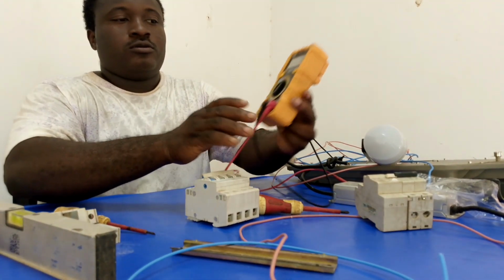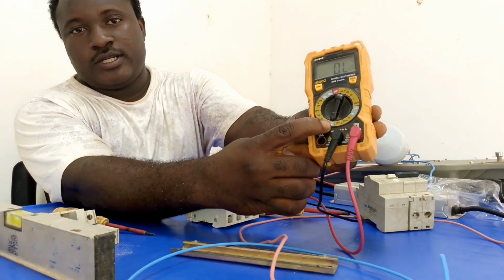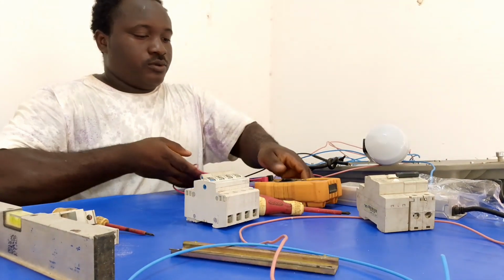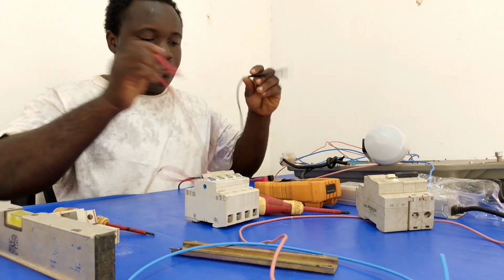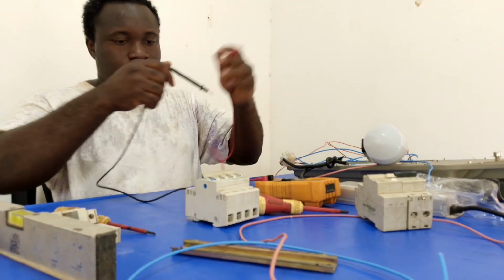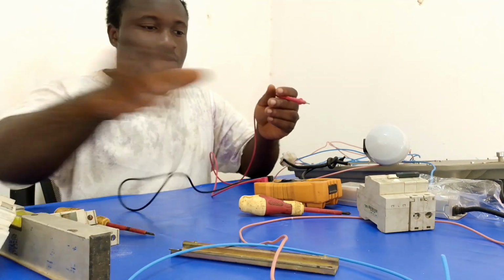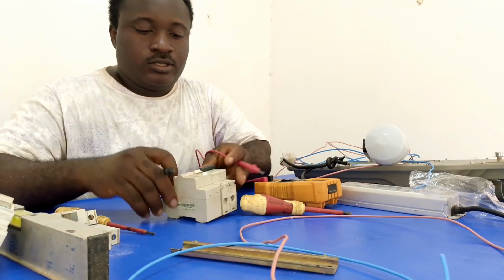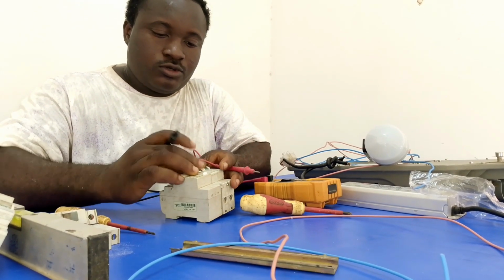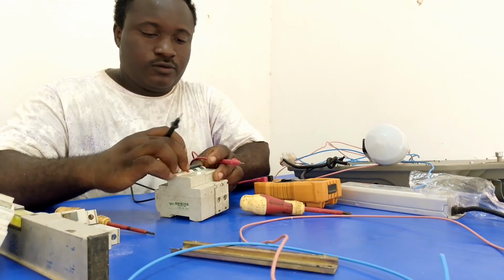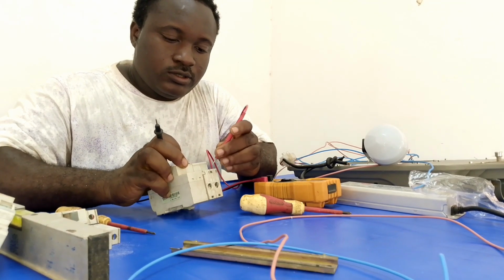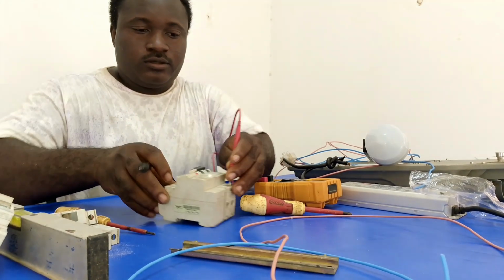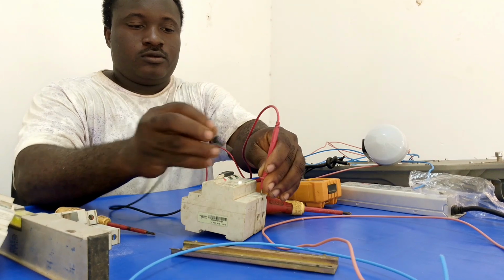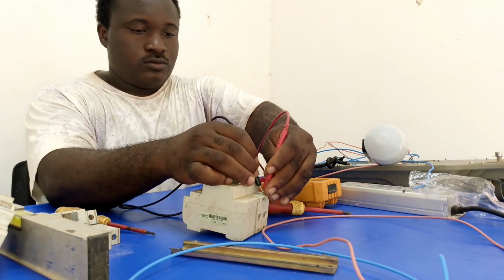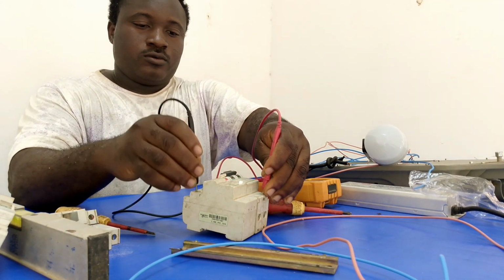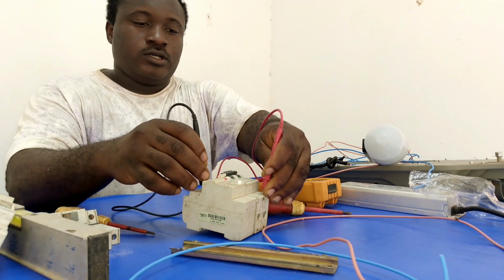You have to put your multimeter on continuity, where the sign is. You take the RCBO, you put it off, and then you check continuity from this terminal, from here to here. I want to see which one is the neutral.